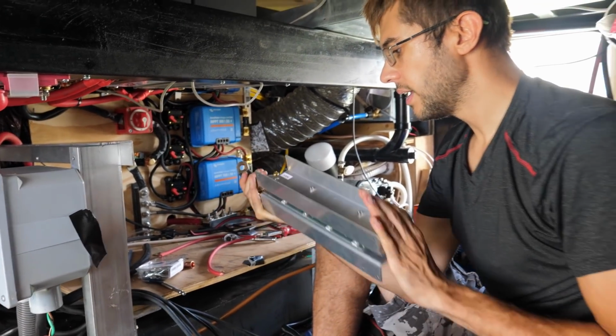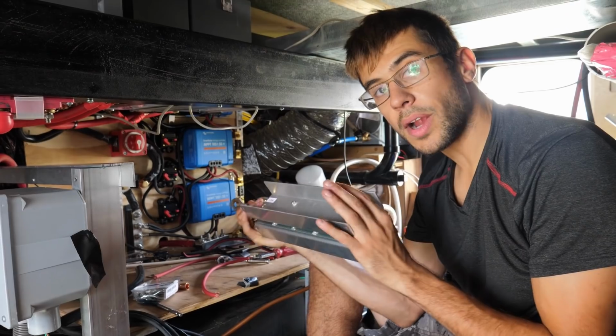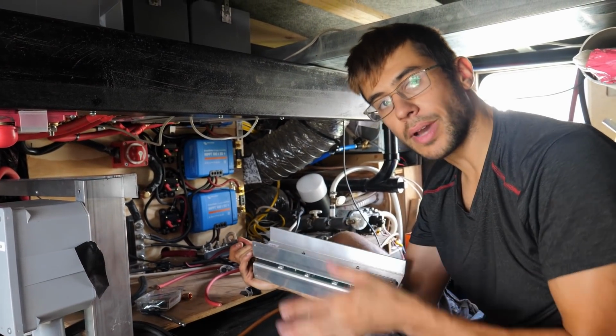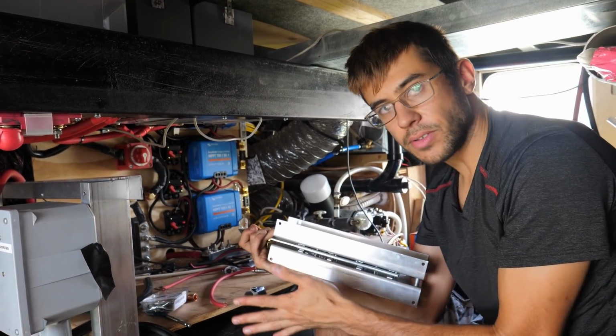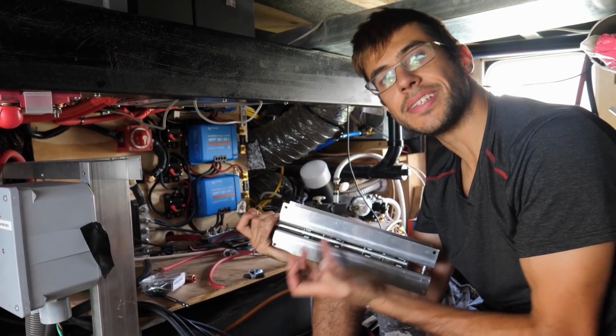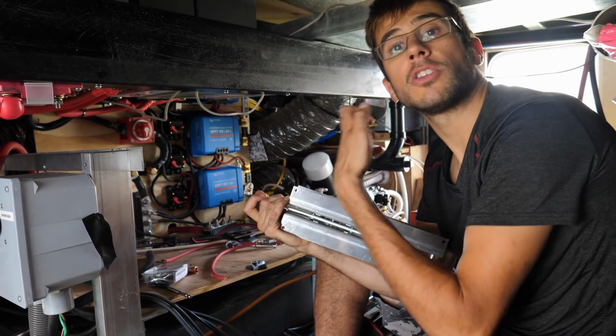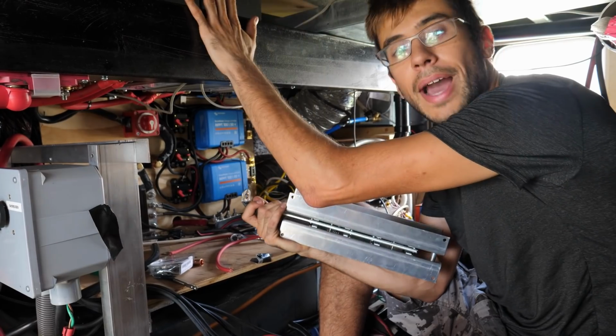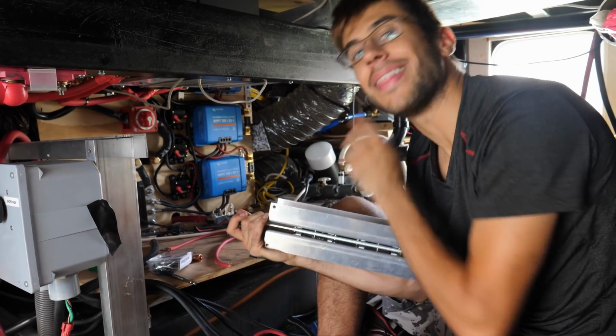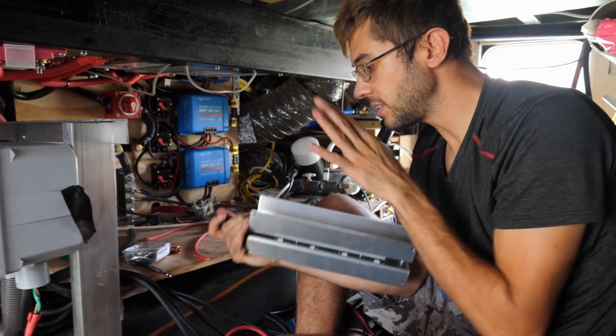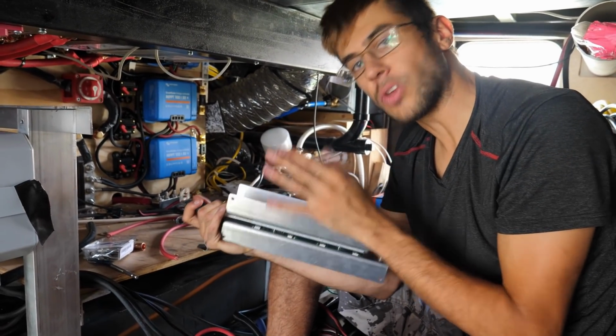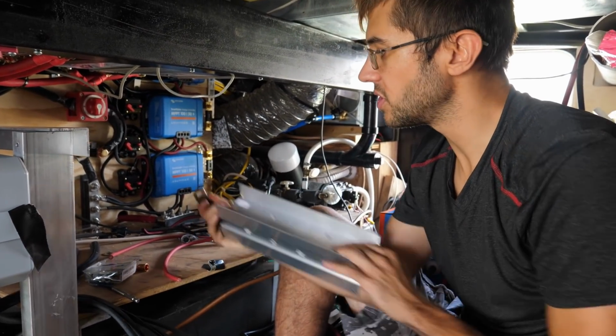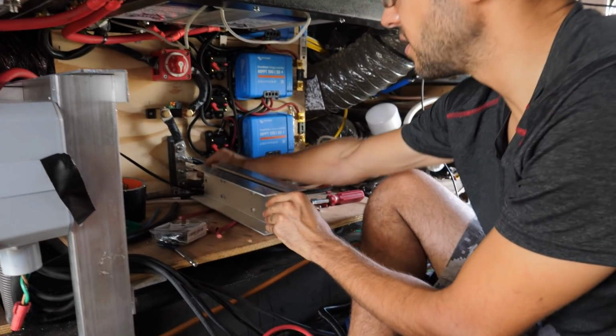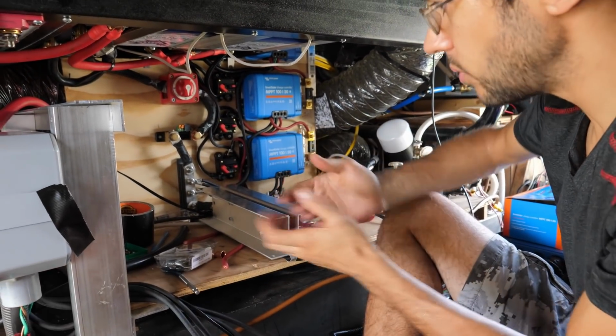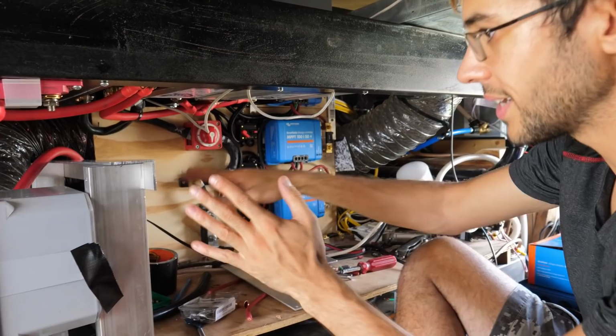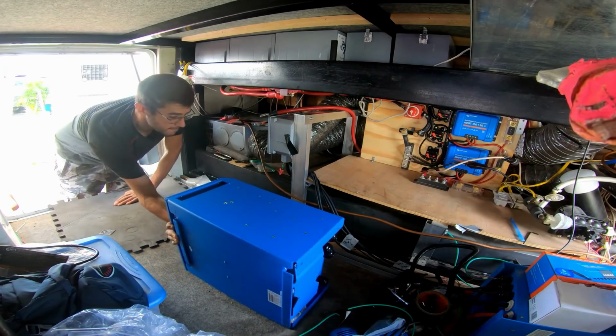Now the CSL is a unique unit that is required for very large inverters in the Battleborn system. This 5,000 volt amp inverter has large capacitors in it that charge so quickly that it'll basically trick the batteries into thinking there's a short in the system and they will shut off. So this is basically an external piece of BMS that is only required for these large inverter systems. So we're going to install this here. This is basically the negative lead which will go into the inverter, and hence the big blank space right here is where the inverter will be installed.